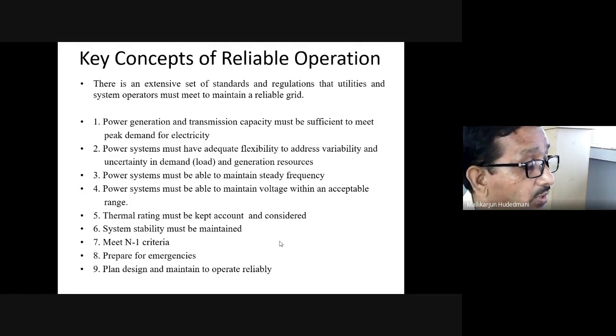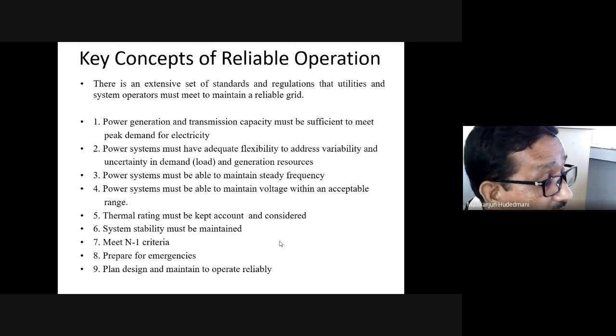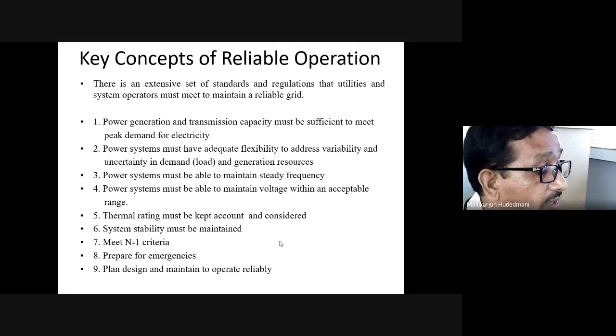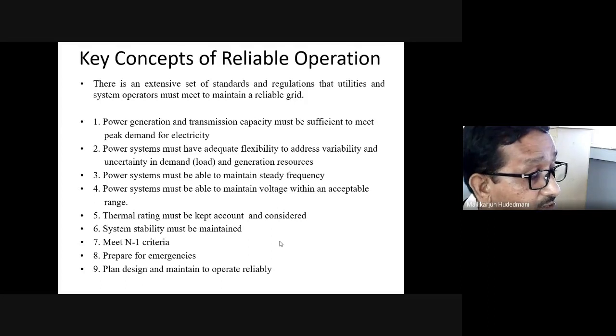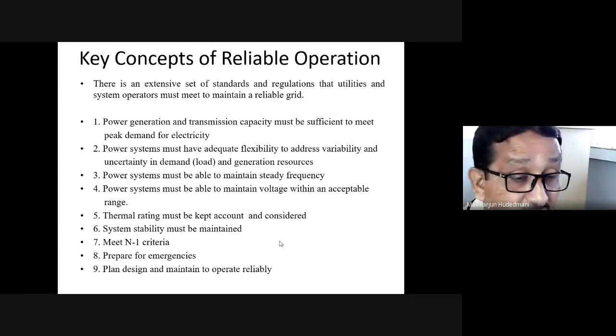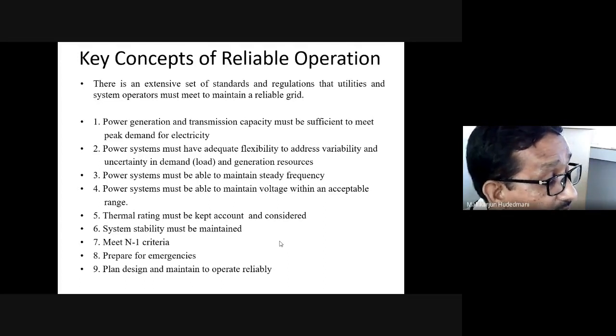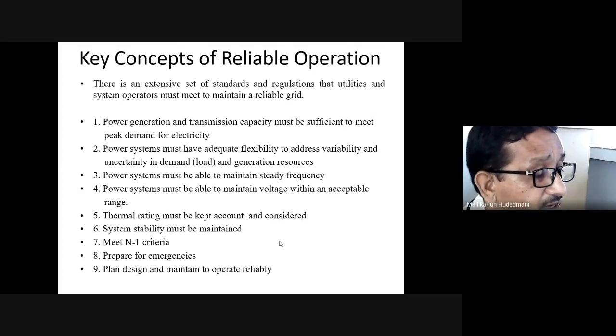In that regard, the capability of that transmission line should be explored up to a good value, and beyond a certain thermal ability, the critical value, I should not load it. Or if there is a criticality or bottleneck issue associated with that particular component as the thermal rating is considered, I must take care of that whenever the component encounters such a situation. It should not be overridden. It should be controlled well within limits so that its service is there for the power system. Else, undue overriding may cause failure, breakdown of that component, and the effect may cascade so that other components get affected due to the failure of the first and second, together in the third or fifth. A series of failures would result.